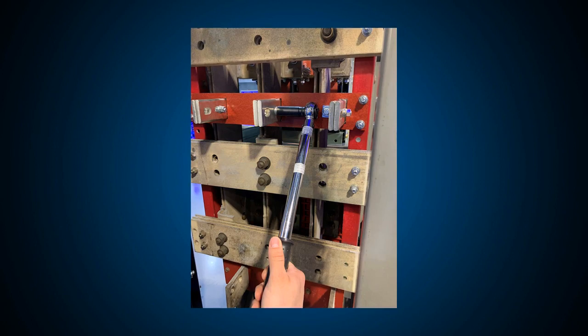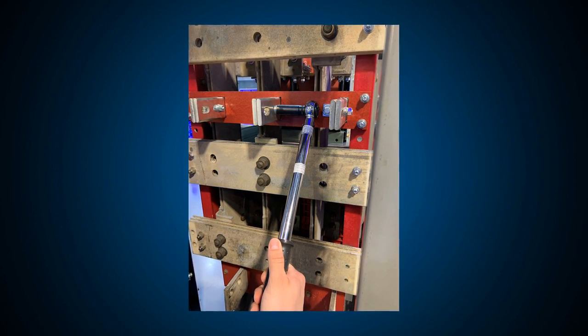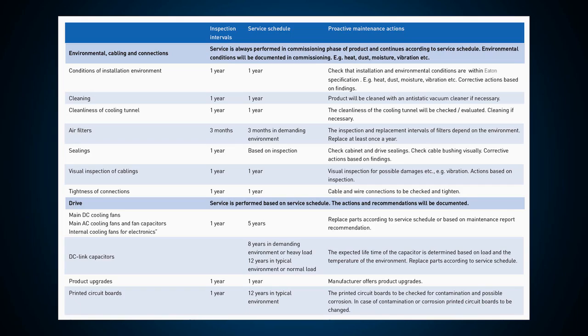Finally, during maintenance, be sure to tighten or torque connection points and hardware. Most issues occur from loose connections, but sometimes over-torquing can be problematic as well. We are often asked, what is the appropriate time interval for testing electrical equipment? The answer, as with many things, is it really depends. Each system is unique, depending on the environment, the use of the equipment, and other factors. Our services group can help you determine what is right for you.